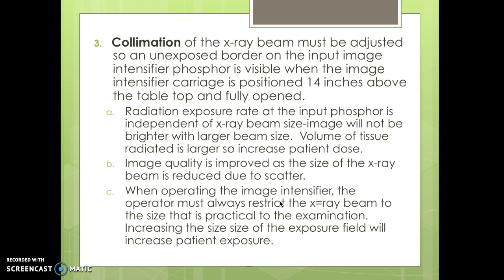Collimation of the x-ray beam must be adjusted so that an unexposed border on the input image intensifier phosphor is visible when the image intensifier carriage is positioned 14 inches above the tabletop and fully open. Radiation exposure rate at the input phosphor is independent of the x-ray beam size — the image will not be brighter with a larger beam size, but the volume of tissue radiated is larger, which increases patient dose. Image quality is improved as the beam size is reduced due to less scatter. The operator must always restrict the x-ray beam to the size practical to the examination.